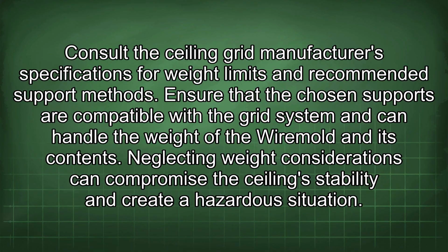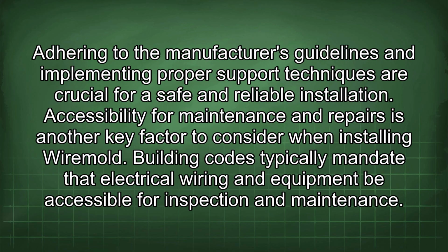Consult the ceiling grid manufacturer's specifications for weight limits and recommended support methods. Ensure that the chosen supports are compatible with the grid system and can handle the weight of the Wiremold and its contents. Neglecting weight considerations can compromise the ceiling's stability and create a hazardous situation. Adhering to the manufacturer's guidelines and implementing proper support techniques are crucial for a safe and reliable installation.